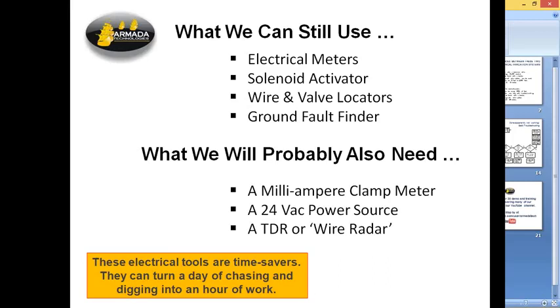Solenoid activator is great, good for conventional systems, but it allows you to test the solenoid inside the valve box to figure out whether you've got a bad decoder or a bad solenoid. So still useful. Wire and valve locators, no matter what you do, you still have to know where stuff's buried, and that means following the main path of the cable. So if you've got one, have access to one, or can rent one, you're good. Pretty important. A ground fault locator is another big deal, because some of the damage that occurs in the field is damage to cables. Besides having a splice issue, and you can even find a wet splice using this actually, it leads you to a place where the insulation's been nicked or the wire's been cut. Great thing, works with all these systems.